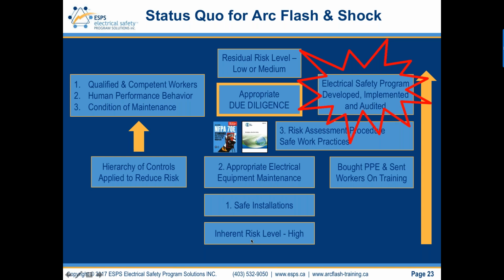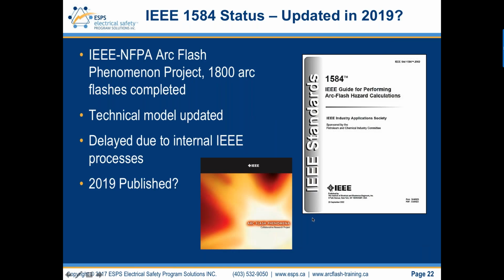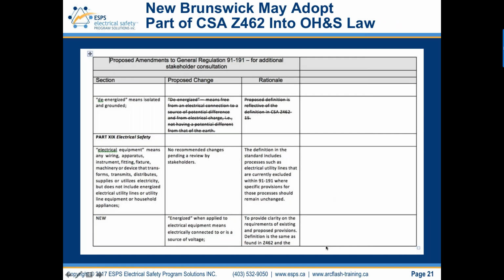So as we move from what was inherently high-risk energized electrical work tasks through this evolution and the latest editions of CSA Z462, we achieve appropriate due diligence as well to OH&S or OSHA regulations. And then the residual risk level will be low or medium. Again, we apply the hierarchy of controls on the left-hand side to reduce the inherent risk, to achieve the residual risk to as low as reasonably practicable.